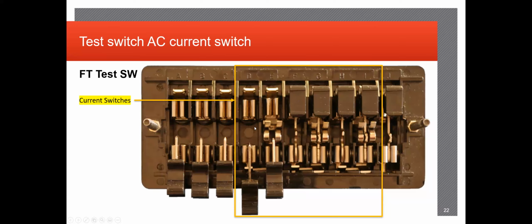The reason why you can identify these test switches to be current switches specifically is based on this little bracket right here and these shorting bars at the bottom. So, just a quick question, does anyone know what would happen if a breaker was in service and it had an associated CT and that CT circuit opened up? Does anyone know what would happen?